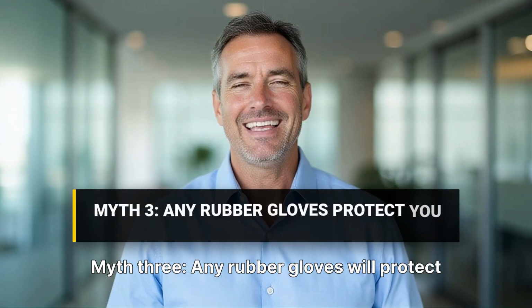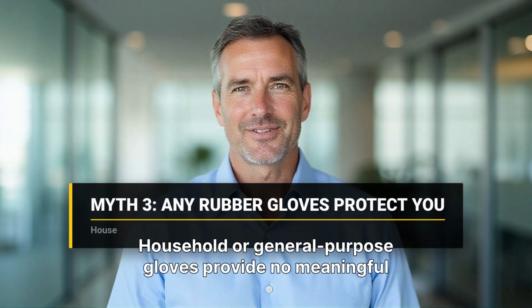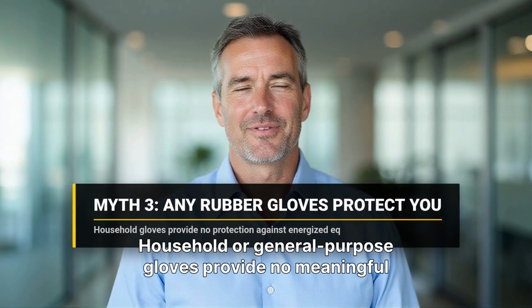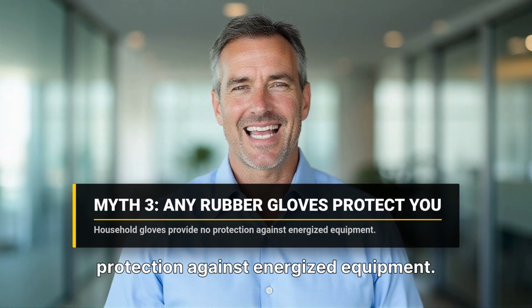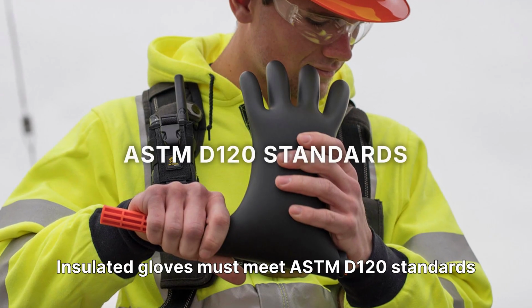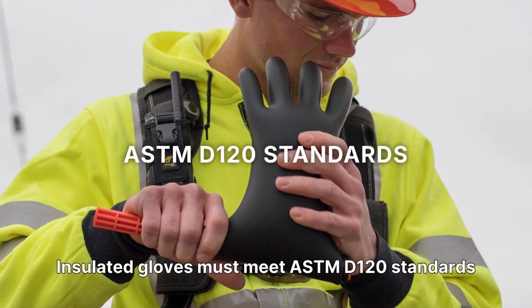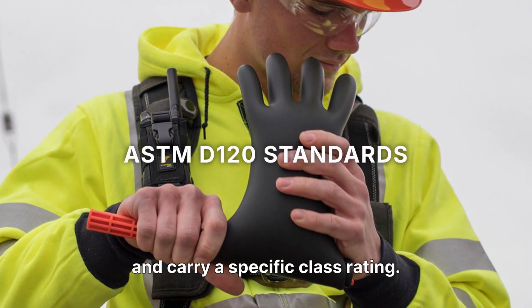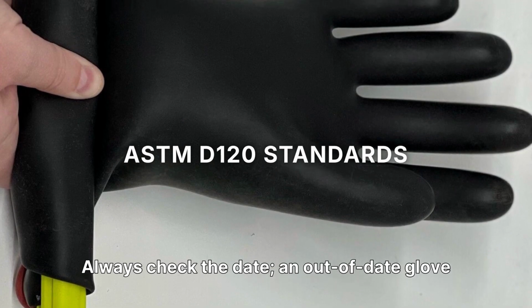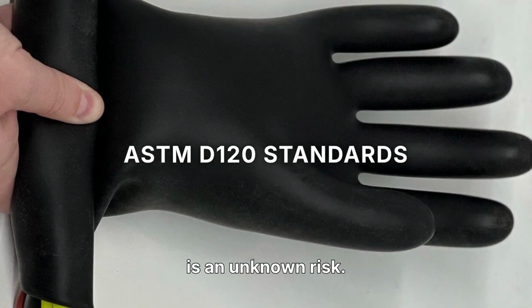Myth 3, any rubber gloves will protect you. Household or general purpose gloves provide no meaningful protection against energized equipment. Insulated gloves must meet ASTM D120 standards and carry a specific class rating. Always check the date. An out-of-date glove is an unknown risk.